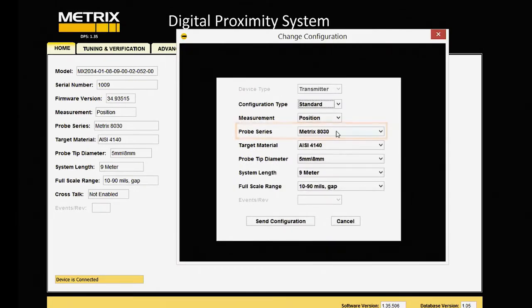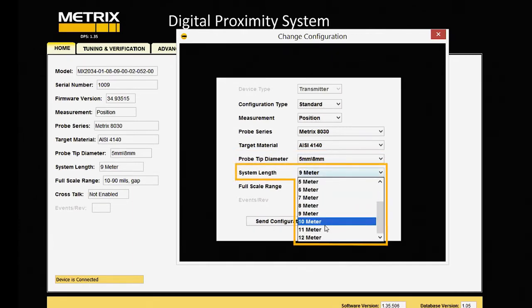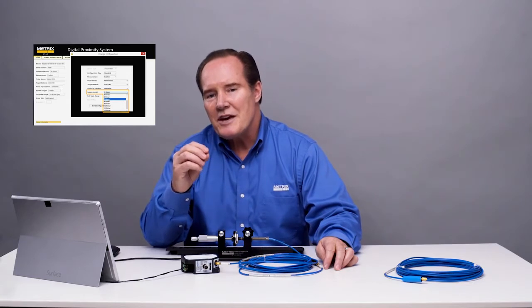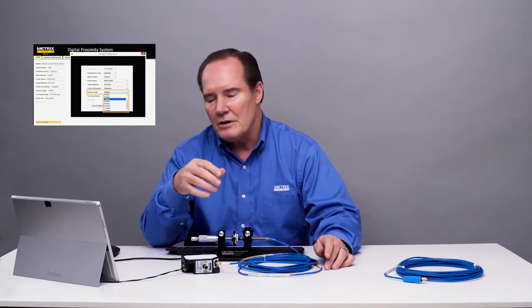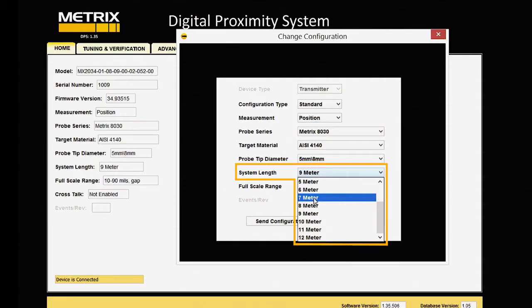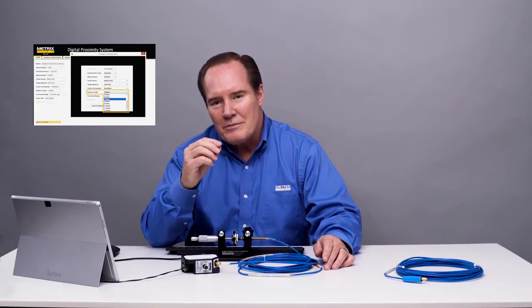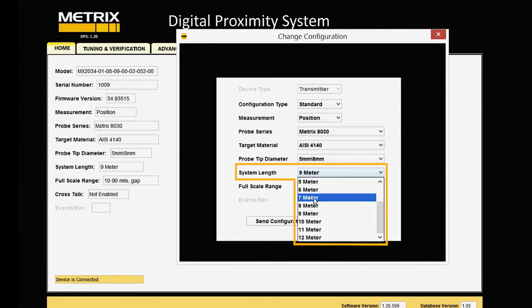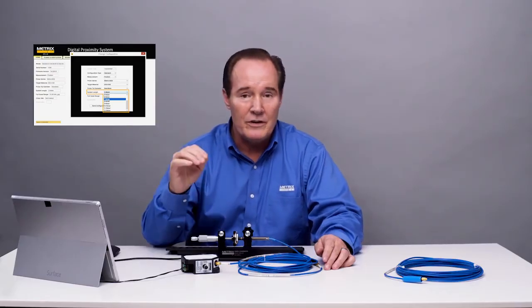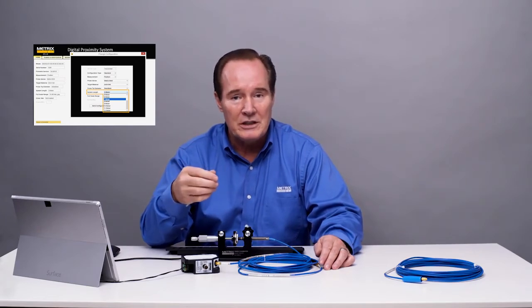We have MX8030 as the probe type, 4140 as the target material. We are still working with the 8mm probe. We've got a 9-meter system length. Now, we cut off 2 meters, so we could just choose 7 meters. What happens if you cut, let's say, 7.5 meters? Let's say that's what you needed in your cabinet, and we don't have a 7.5-meter selection in our software. Well, you can pick 7 meters or you can pick 8 meters, and if you're close, you'll get a curve from your verification and you can do a custom calibration. That's the power of the digital proximity system. You can make it perfect.